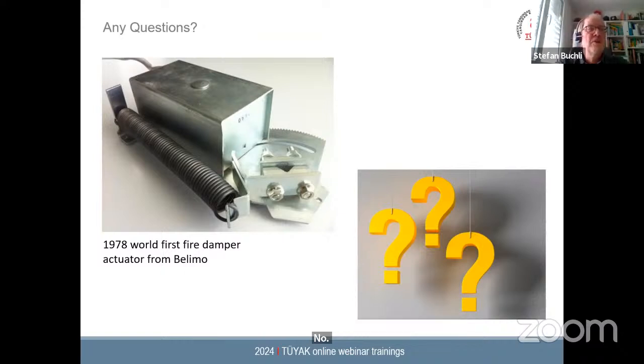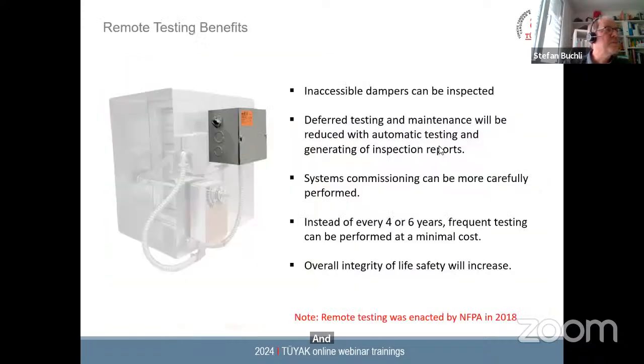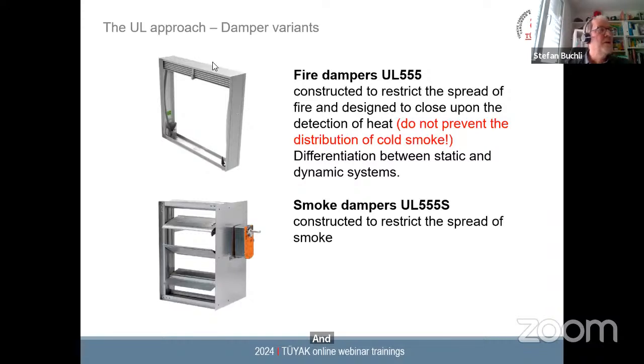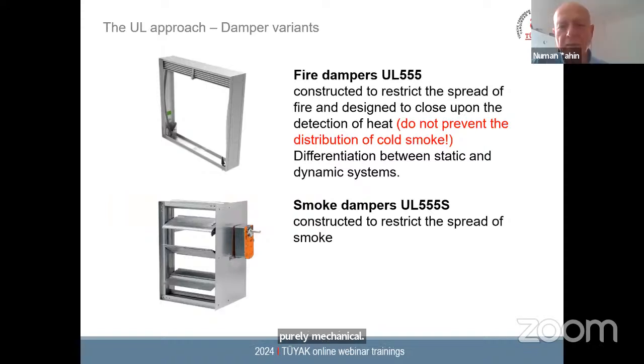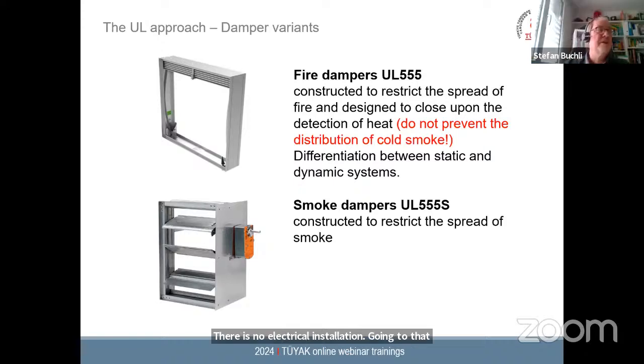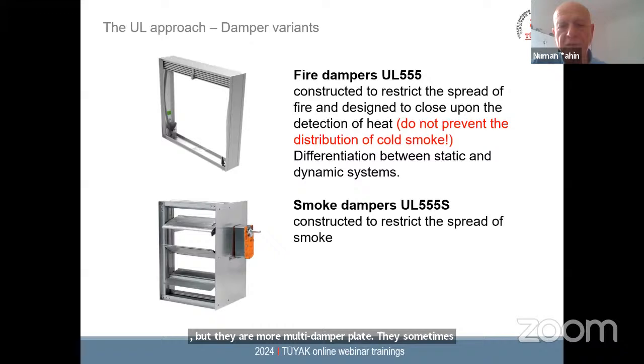If you look at the UL world, maybe I go back, you still see my slides. If I go back to the fire damper UL 555, the curtain damper, it's purely mechanical. There is no electrical installation going to that damper. And there are some installations in the Middle East, but they are more multi-blade fire dampers. Sometimes they have an electrical switch in the closed position, but not very often. So it is not mandatory.